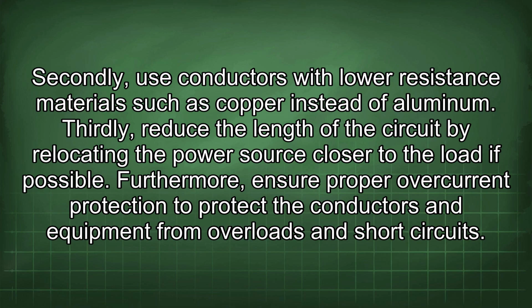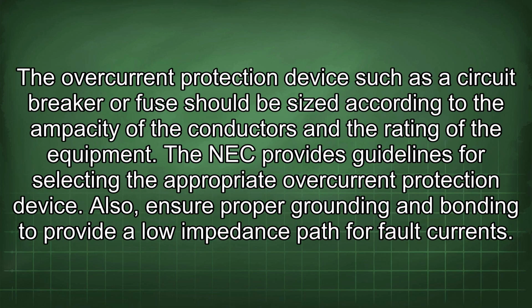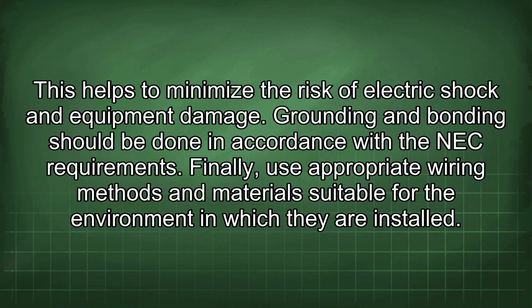Furthermore, ensure proper overcurrent protection to protect the conductors and equipment from overloads and short circuits. The overcurrent protection device such as a circuit breaker or fuse should be sized according to the ampacity of the conductors and the rating of the equipment. The NEC provides guidelines for selecting the appropriate overcurrent protection device. Also, ensure proper grounding and bonding to provide a low impedance path for fault currents. This helps to minimize the risk of electric shock and equipment damage. Grounding and bonding should be done in accordance with the NEC requirements.